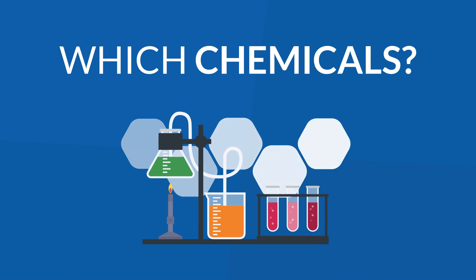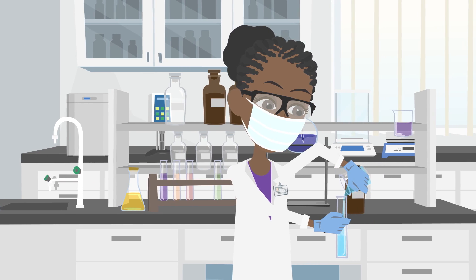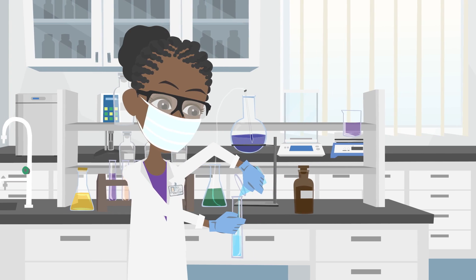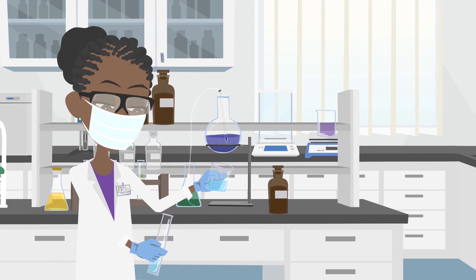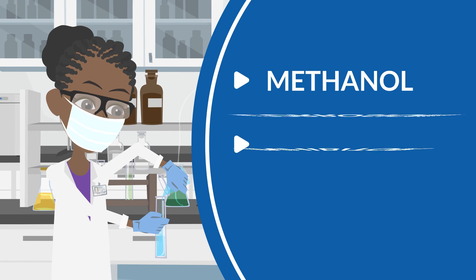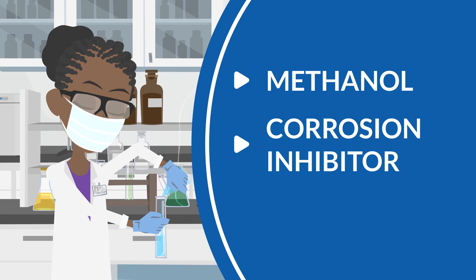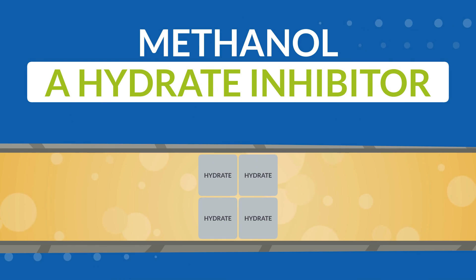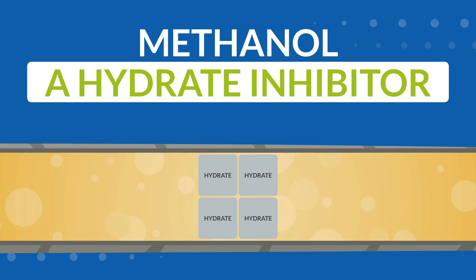Which chemicals are used in the oil and gas injection process? There are different chemicals which can be used in the oil and gas injection process. For example, methanol, corrosion inhibitor, or H2S scavenger. Methanol is used as a hydrate inhibitor since hydrate solidifies and can cause flow restrictions or plugging in wells and flow lines.